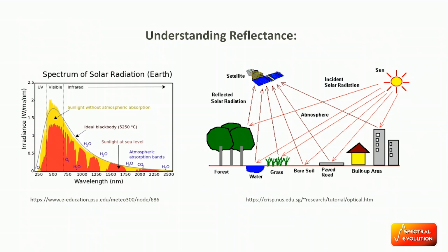So when you take a white reference measurement with a white plate, the idea of a white plate is to get a representation of the total energy or light that you're measuring so that you can get a good reflectance measurement. So you take a measurement of the total light, then you take a measurement of the target, which is the light that's reflected off of an object, and that should be characteristic of the material that you're targeting.